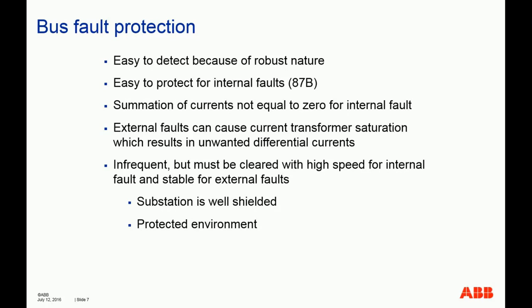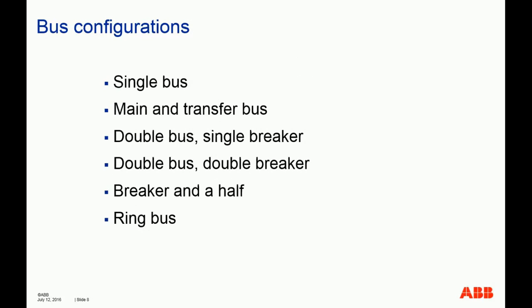However, the catch is that an external fault could cause current transformer saturation. Once the current transformer, which is your sensor, is saturated, it will not mirror or measure the fault current accurately, and that would also cause misoperation. The occurrence of a fault is infrequent, but it must be cleared with high speed for an internal fault, and the scheme must be stable for an external fault, as I mentioned.